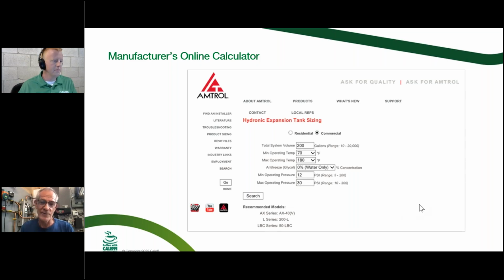I was going there thinking I'd find one the size of a compression tank with a calculator, and it's a conversion, not a sizer, but I think there are some plain steel tank compression ones. If not, the book goes through the factors that you need to use to get that. And the interesting thing about the one example I talked about in the Amtrol book, where that 7,000 gallon system, here was something that blew my mind. I think it was like a 1,200 gallon compression tank was going to be required, and like a 60 gallon diaphragm type tank for the same system.